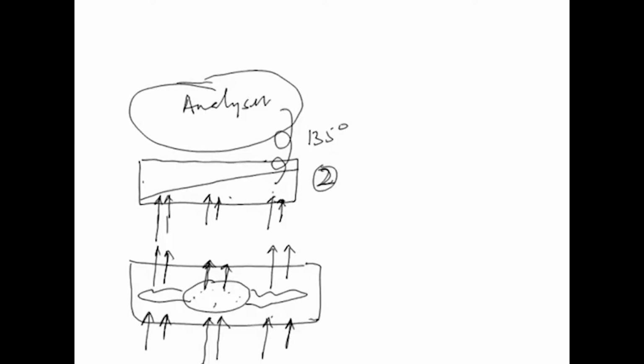Light from the first prism, prism number 1, goes through and passes through the specimen. This light was single and now it is sheared. All the parts of this prism are sheared, and the light passes through the condenser lens, focused onto the specimen. The specimen might contain different things, so light is retarded differentially here. These two lights then pass through the objective into DIC prism number 2, where they are combined and are now polarized at 135 degrees.